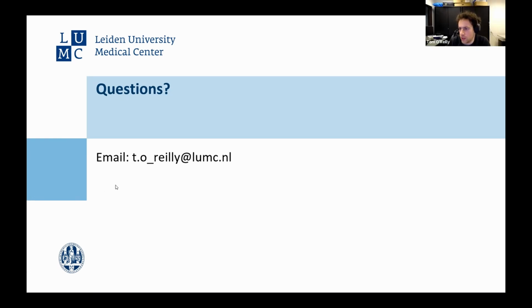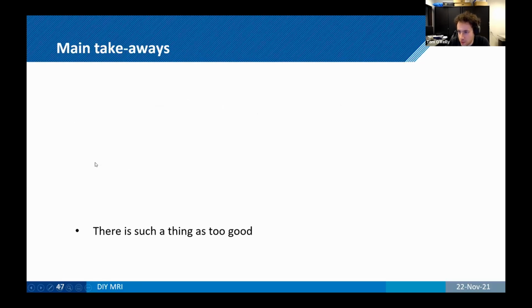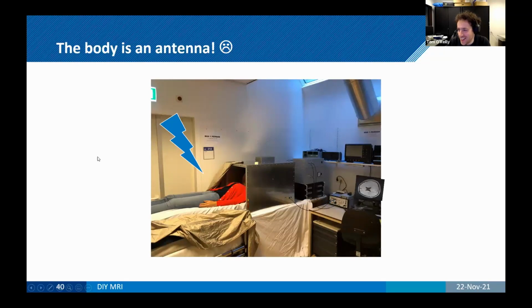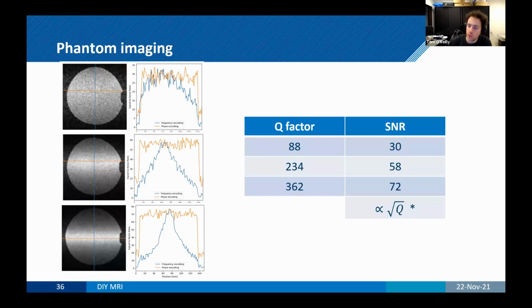It's a really good question, because I don't have the answer for you. Quality-wise, we're looking at using some of the methods from high field systems, where you can use something called preamplifier decoupling to reduce the coupling between your coil arrays. You have a low input impedance preamplifier and a quarter wavelength impedance transformer, which transforms it to a high impedance on your coil. You use that high impedance as a lossless way of destroying the quality factor of your coil. So you destroy the quality factor, but you don't add losses, so you should keep the same SNR.